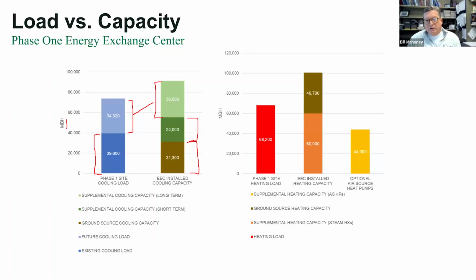I've got it juxtaposed here, but there's your ground source. The brown is the ground source, and that can't meet this whole building load that's required in the winter. So we had to do this supplemental heating, which is this guy. And we provide that, like we said, with condensing boilers or steam heat exchangers, or then the option on top of that was it wouldn't serve you in the middle of the winter, but in the fall and spring shoulder periods, we have air source heat pumps to kind of supplement some of this boiler operation. And that's another emission-free, scope one emission-free heating method. So that's the mix of what we had recommended to them for their plant capacity.